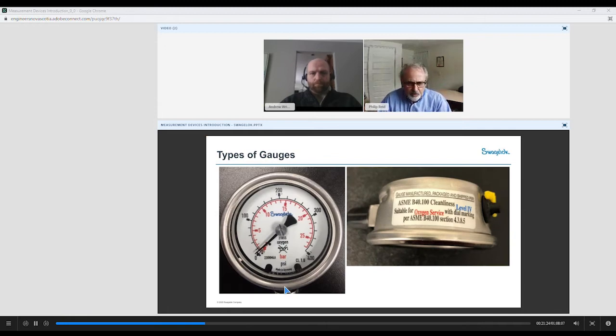So having said that, a couple of the most common gauges that we get into for specialty applications will be oxygen. And an oxygen cleaned gauge will have the symbols on the front of it, no oil. It will state oxygen. Here we see the material of construction on the wetted components. There's a bit of other information on the front here that we won't get into today. But this gauge is a compound gauge, again, reading positive pressure up to 400 psi or up to approximately 30 bar. And again, this is a removable front with a, pardon me, this does not. This has a crimp front, so therefore you can't get in to calibrate this gauge.